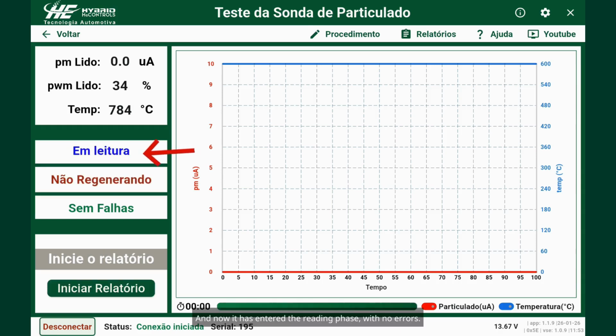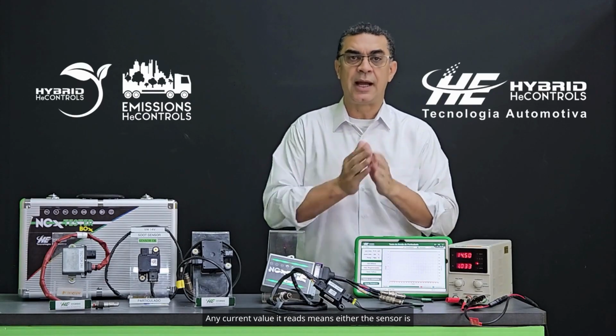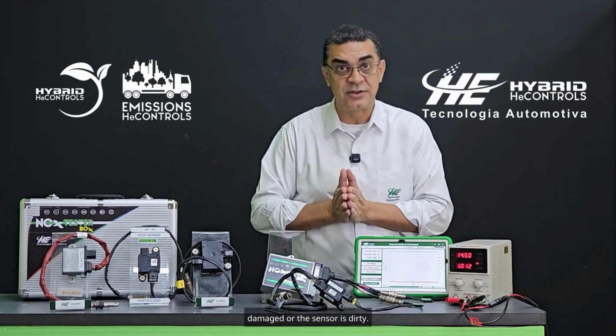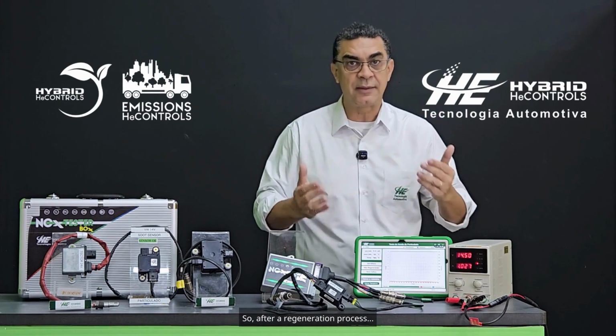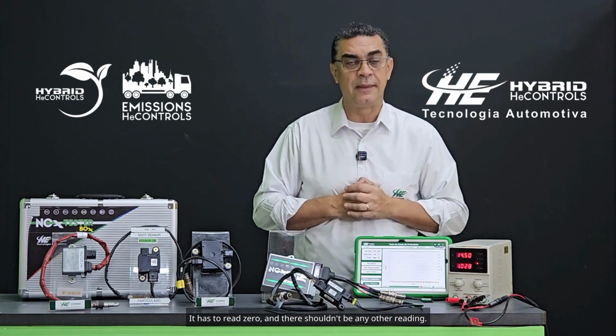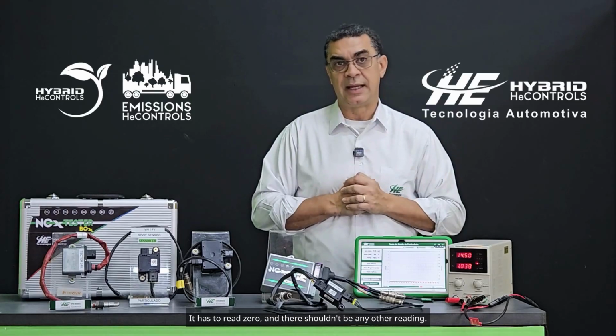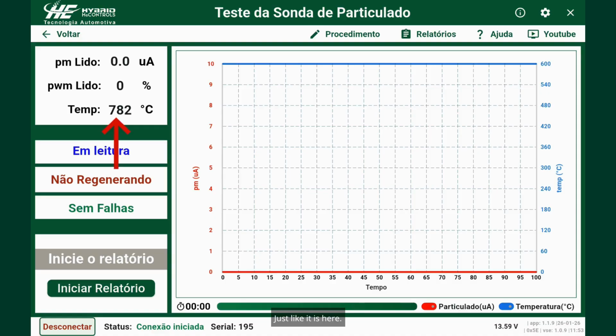And now it has entered the reading phase with no errors. Now is the time when I will see what it is reading. And it keeps reading 0, and that's how it should be. It has to be 0. Any current value it reads means either the sensor is damaged or the sensor is dirty, right? So after a regeneration process, it has to read 0, and there shouldn't be any other reading, just like it is here. The temperature begins to decrease when it enters the reading phase.